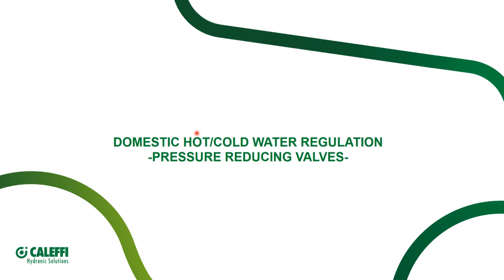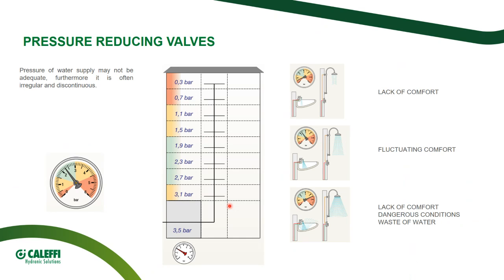We are missing the last regulating element, that is the pressure controlling valves. Also, the pressure is a hectic parameter to deal with, especially in medium-big buildings. So this is the typical situation in a medium-big building. I have an inlet pressure value in the building, and then I have a distribution system. Here I have a multi-story building entering with 3.5 bar. Because of gravity and linear pressure drops, I am reaching the highest dwellings with a non-sufficient pressure value. And this translates into lack of flow rate and lack of comfort.